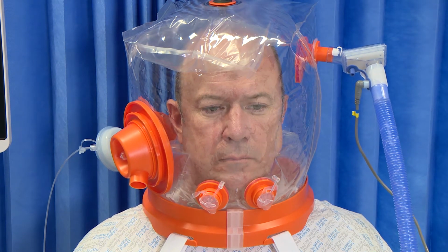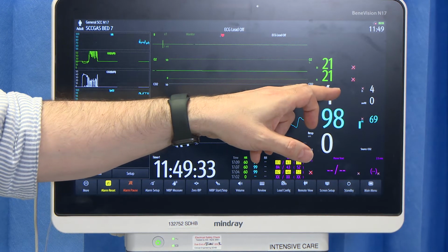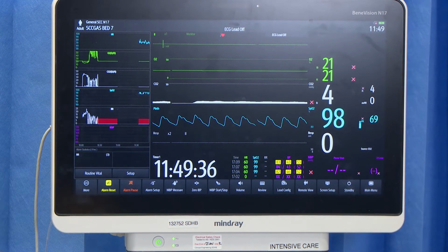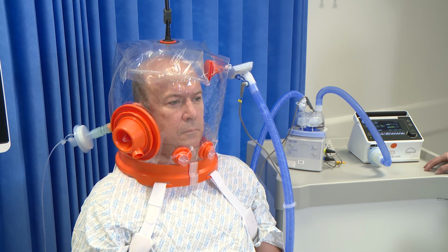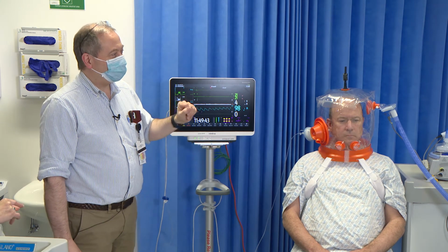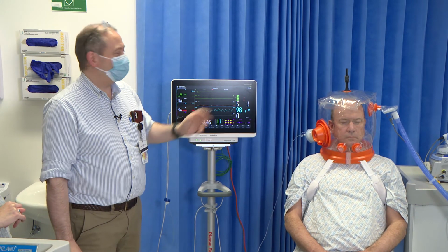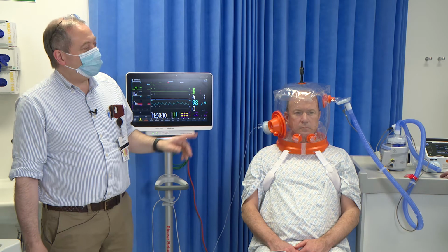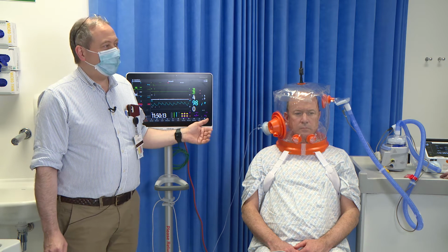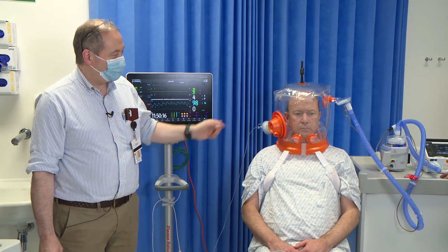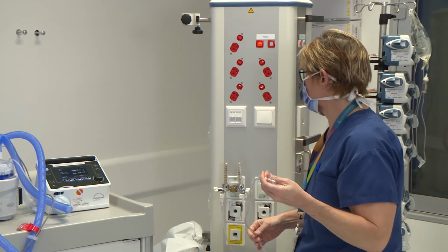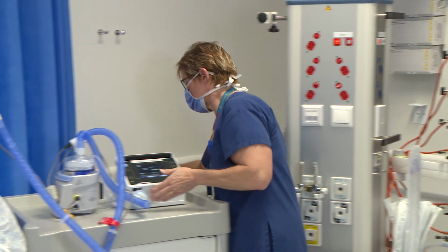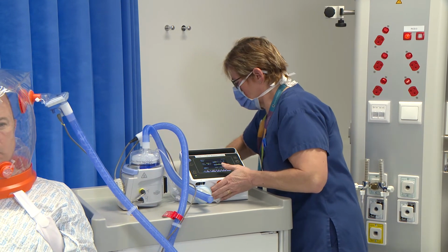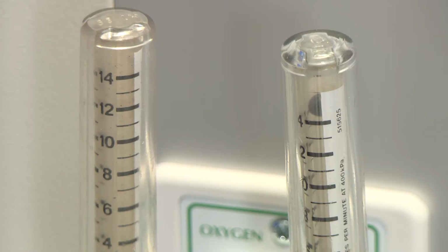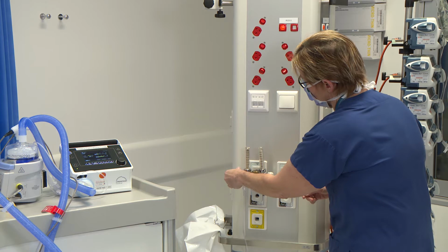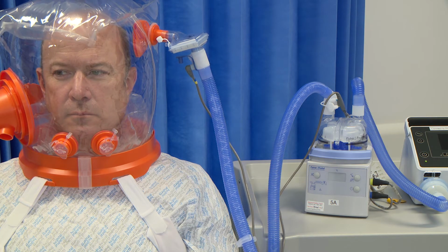If this number was rising, we'd be concerned that he was rebreathing his carbon dioxide, and we'd have to check the flows were high enough. But as I say, once we know the characteristics of our home CPAP machine, and provided the flows are above around 40 to 50 litres a minute, there shouldn't be any rebreathing. We're not currently using any additional oxygen, and we can apply additional oxygen to the helmet using the CPAP machine. Tony is going to connect some supplemental oxygen to the CPAP machine, and we're going to set it to 15 litres per minute, and we'll see what the FiO2 is in the helmet on the monitor here.